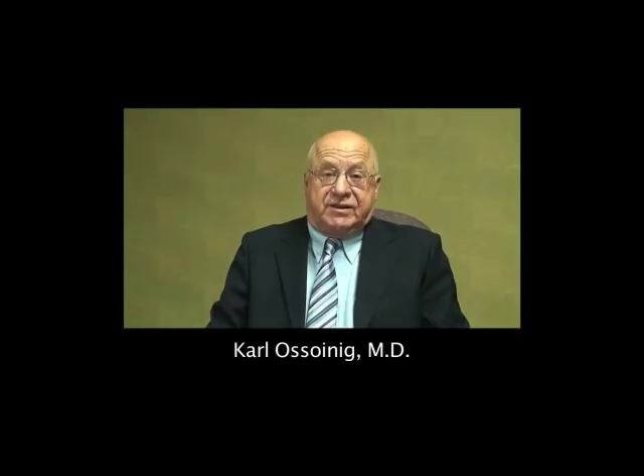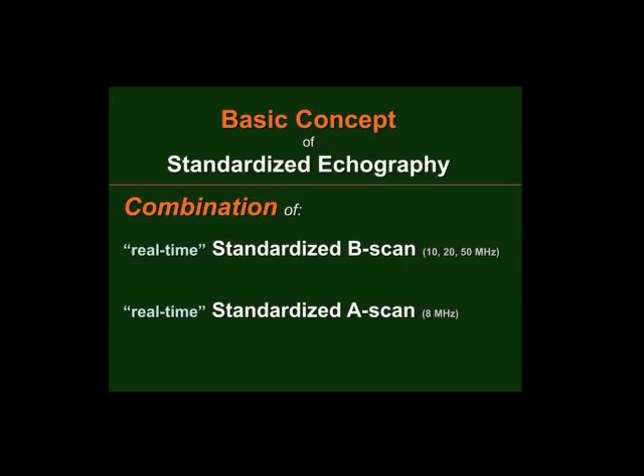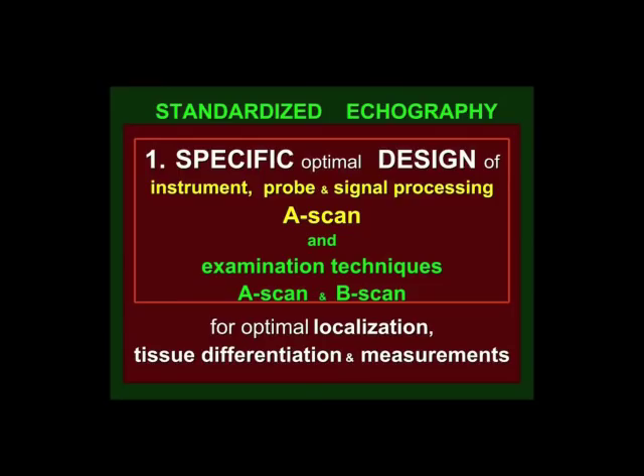What is standardized echography? It's an ultrasonic diagnostic method developed to offer the fullness of capacities and diagnosis available for ultrasonography. The A-scan shows amplitudes, but the height of these amplitudes means nothing unless all the parameters of the instrument and technique that influence these amplitudes are standardized. The A-scan instrument and probes are optimally designed for this purpose, allowing tissue differentiation and measurements that are most precise and reliable.